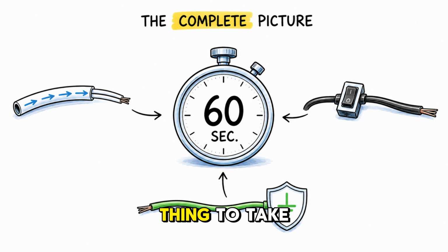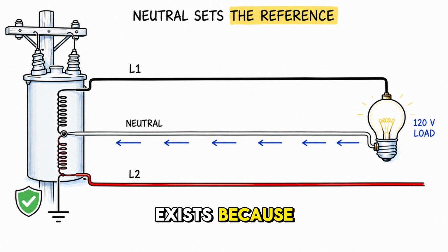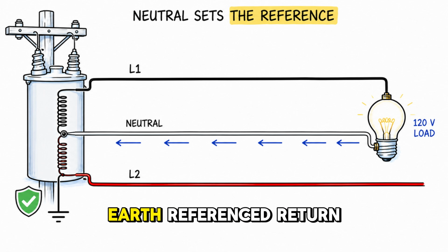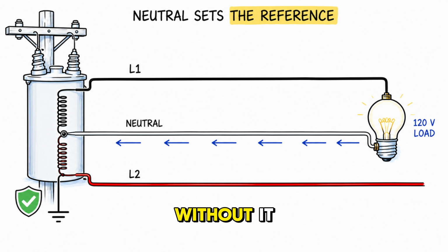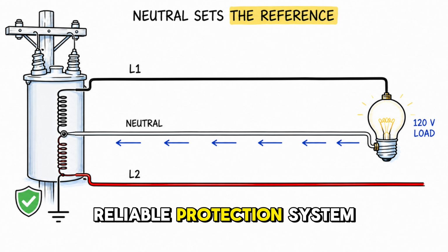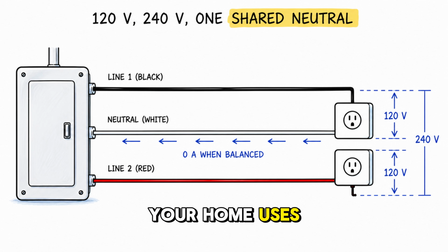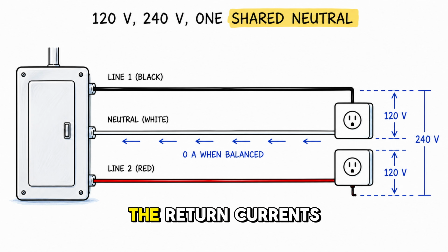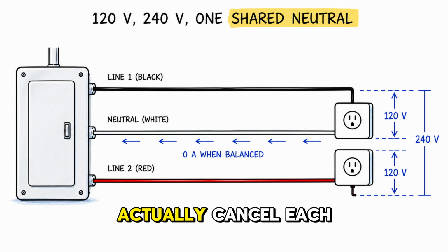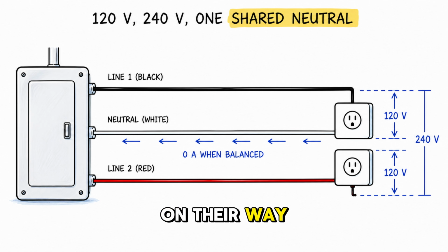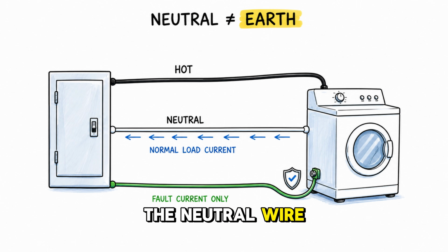There is one final thing to take from this video. Let us close with the complete picture in 60 seconds. The neutral wire exists because alternating current voltage needs a stable, earth-referenced return path. Without it, you cannot design a reliable protection system. Your home uses 120 volts from live to neutral, and 240 volts from line 1 to line 2. Instead of stacking up, the return currents from opposite lines actually cancel each other out on their way back to the panel. The neutral wire and the earth wire are absolutely not the same thing.